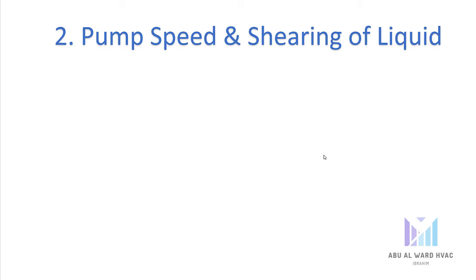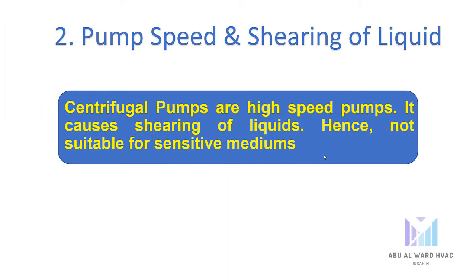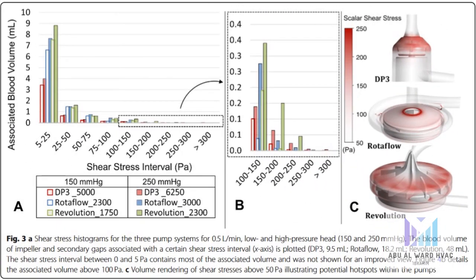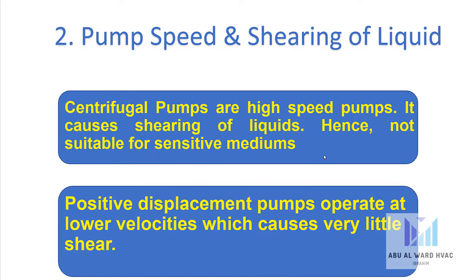The second aspect is pump speed and shearing of liquids. Centrifugal pumps are high-speed pumps, which causes shearing of liquids, making them not suitable for sensitive mediums. Positive displacement pumps operate at lower velocity, which causes very little shear.